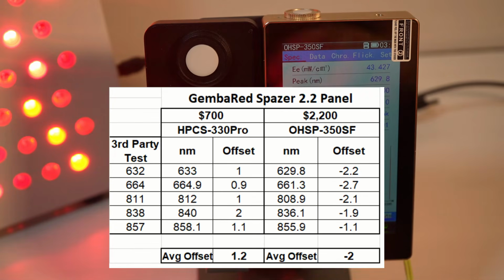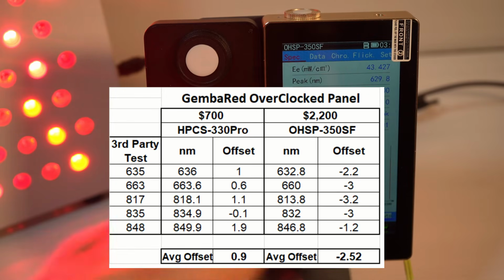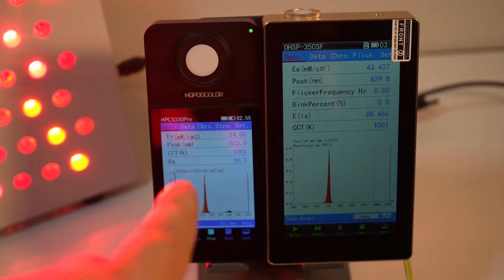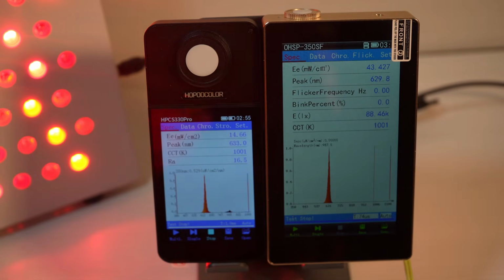I've actually done a bunch of testing. I'll just put it on the screen now. It's a very consistent pattern that this one's actually closer. It's just high by 1 nanometer compared to third-party measurements, and this one's on average low by about 2 nanometers. Like I said, that could be just calibration drift, since this one's newer and this one's older, or it could just be manufacturing variability, and that's what they kind of warned me of.